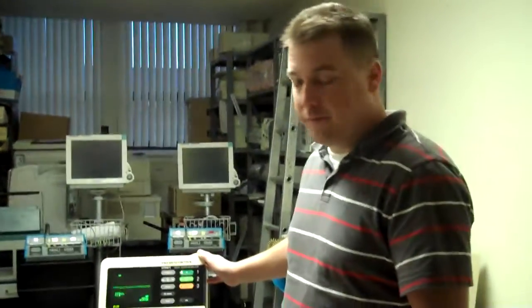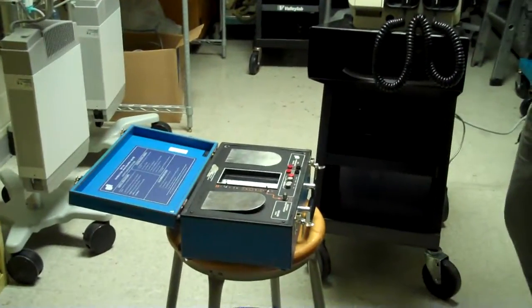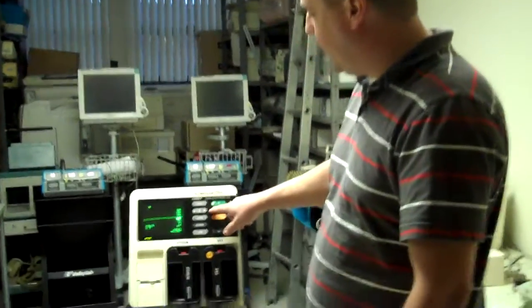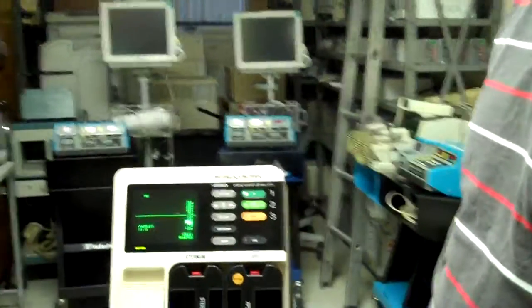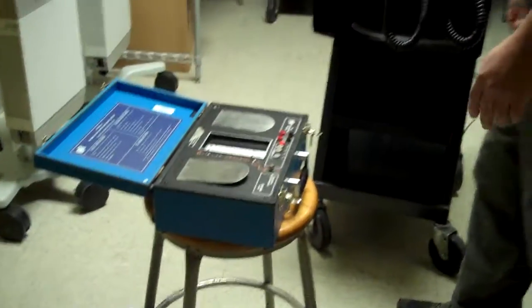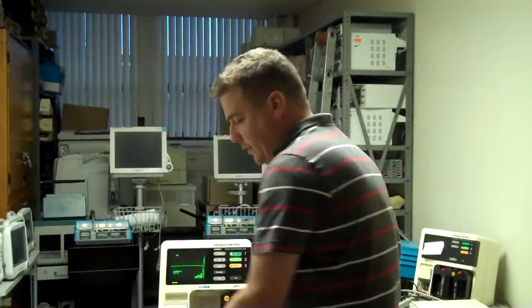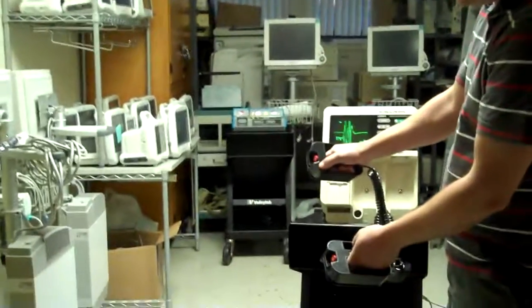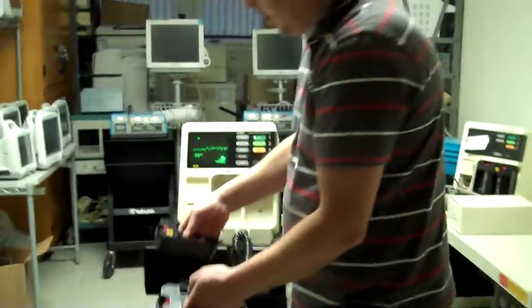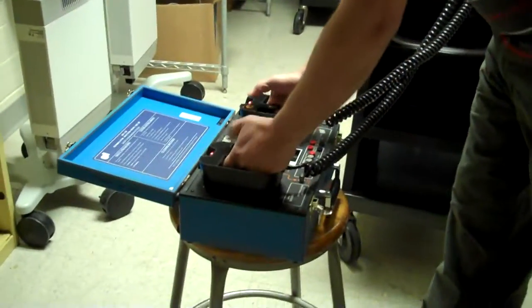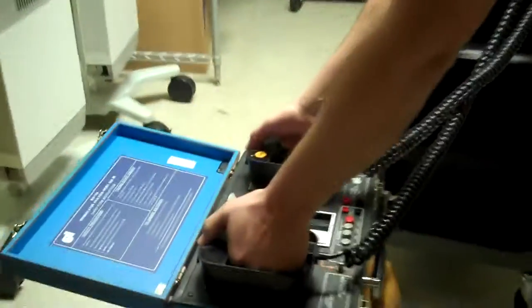So what we're going to do is select 3 energy levels and discharge them into the analyzer, and just make sure that what it's saying it's putting out is actually correct. So we'll start with a low value, and we'll go for 10 joules. I'll check my range here, make sure that we're going to be at 50, so that's plenty of room in there. So I'll take my paddles here, I'm going to go ahead and charge them up. Doesn't take very long to charge up to 10 joules. We'll place them on the pads here, and then we'll discharge and see what we read here. And we're right at about 10, so that looks pretty good.